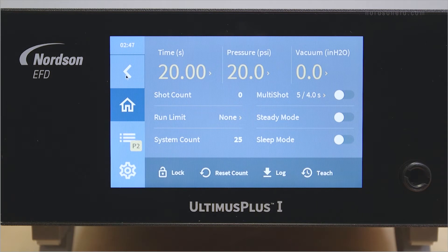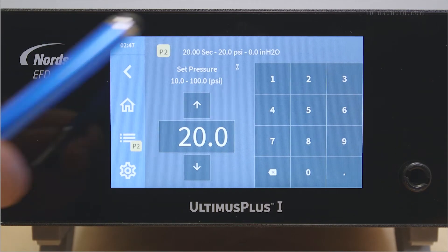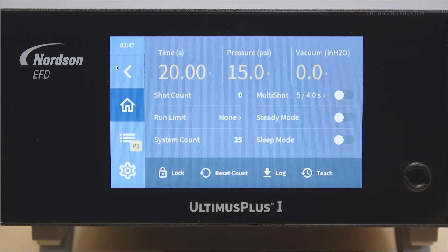The UltimusPlus I ranges from 10 to 100 psi and the UltimusPlus II ranges from 0 to 15 psi. To change the pressure, press the pressure section on the touch screen. Enter a pressure value and wait for the UltimusPlus to accept it. Then hit the back arrow to return to the home screen.